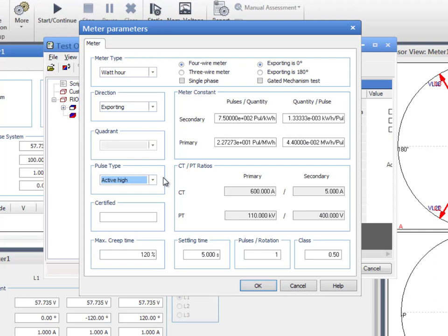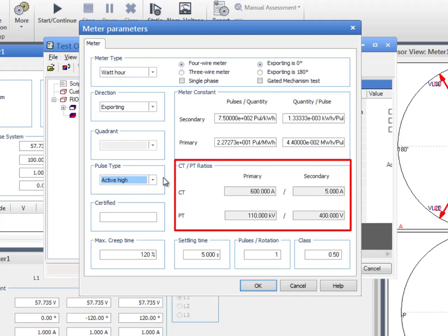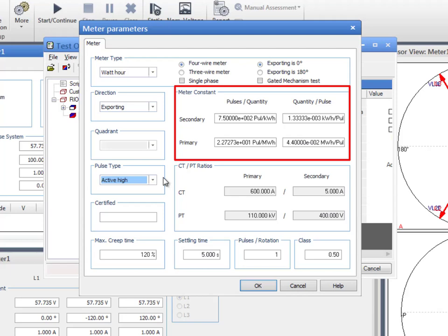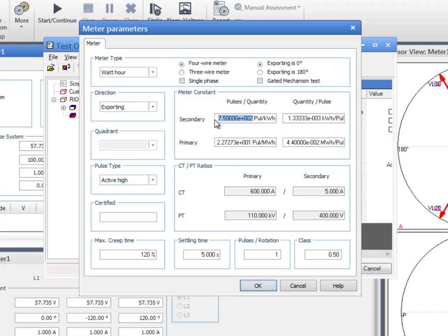Our meter under test counts on active high pulses, which is on the rising edge of the measured pulse. The CT and PT ratios are taken from the device block. If necessary, go back to this block to modify these values. The meter constant is critical for the conversion of pulses into a measurable quantity of power. The meter constant can be entered into one of these fields either as a primary or secondary value, and the remaining three fields are automatically populated according to the CT and PT ratios.